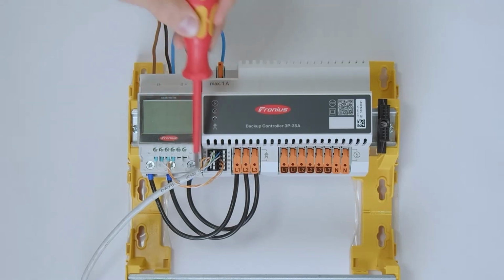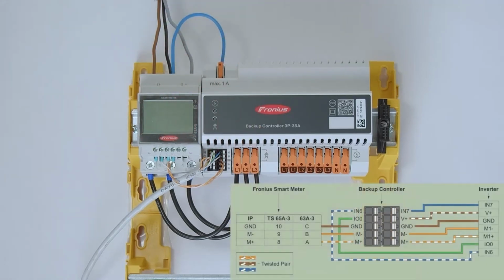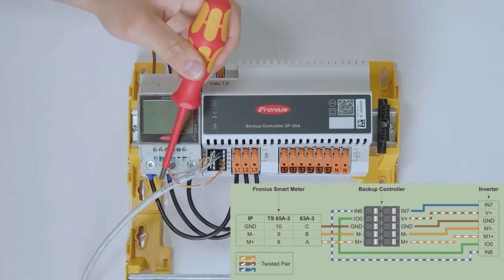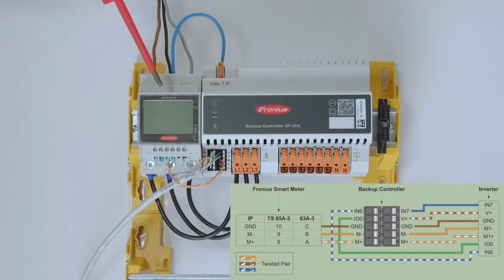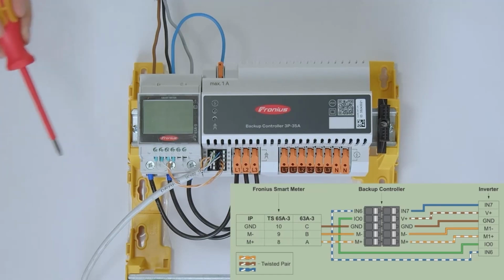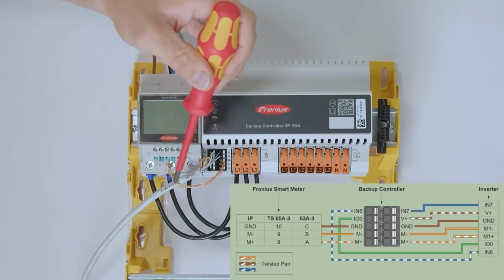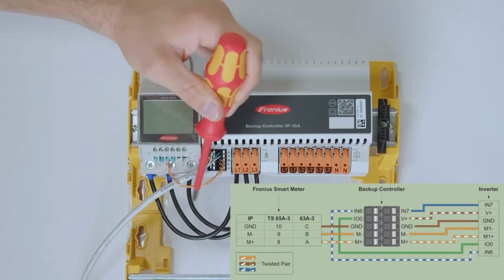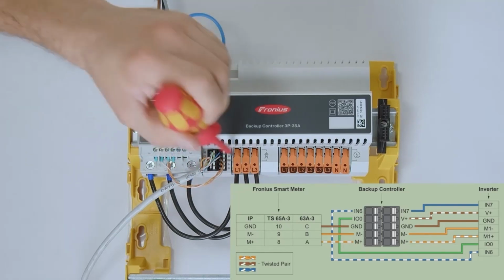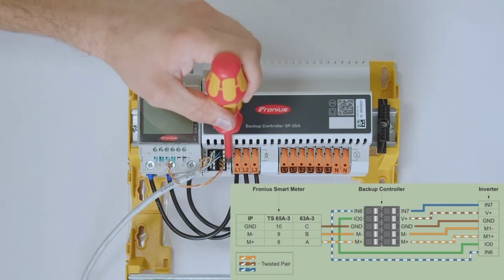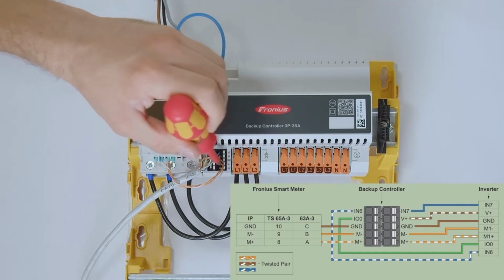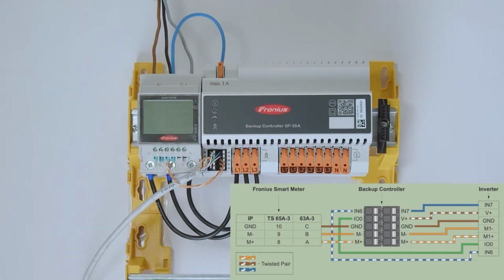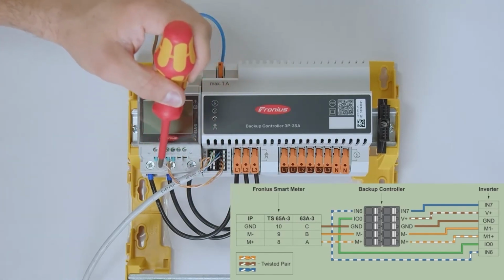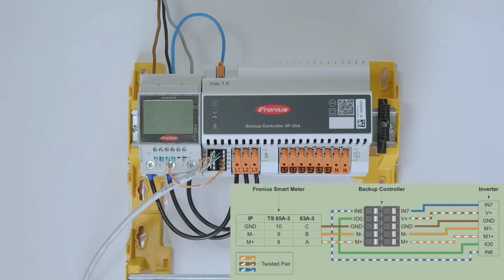Furthermore, we need of course a data communication for the backup controller. And this data communication, first up is our Modbus RTU communication between the Fronius smart meter and the Fronius inverter. To have a convenient way of installation, you can now use the Modbus RTU line coming from the Fronius smart meter directly on the backup controller. Please note, this line is only driven through the backup controller and you can exit it again to go to the Fronius inverter directly. So this is just for a convenient installation. If you don't want to do this, you can directly go from the smart meter to the inverter.